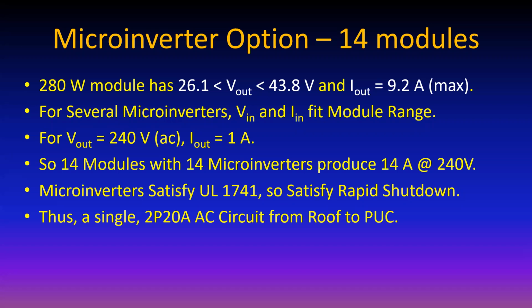Furthermore, the microinverters do maximum power point tracking on the module to which they are connected. So if you've got one module that's shaded and everyone else is not, or 2 modules are shaded, whatever, only those 2 modules are affected, and the rest of the array works just fine. So a single 2-pole 20 amp circuit works fine here because a 15 amp isn't quite big enough. You need 125% of that 14 amps, and that 15 amp doesn't quite do it.